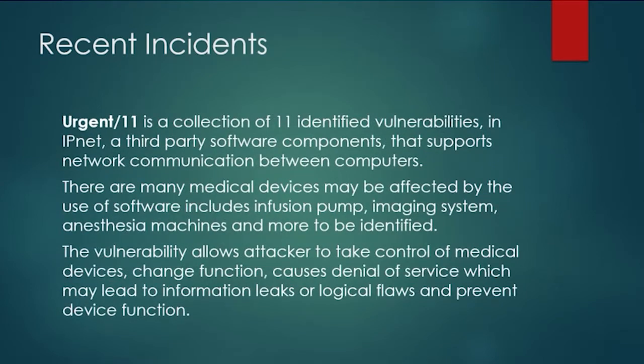URGENT/11 is a collection of 11 identified vulnerabilities in IPnet, a third-party software component that supports network communication between computers. Many medical devices may be affected by the use of this software, including infusion pumps, imaging systems, anesthesia machines, and more to be identified. The vulnerabilities allow an attacker to take control of medical devices, change functions, and cause denial of service, which may lead to information leaks or logical flaws and prevent device function.